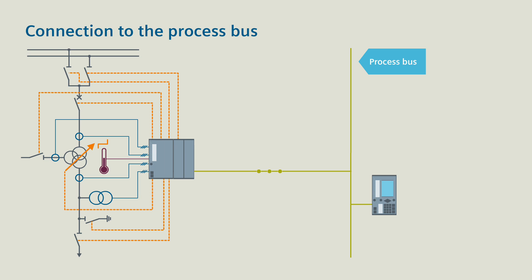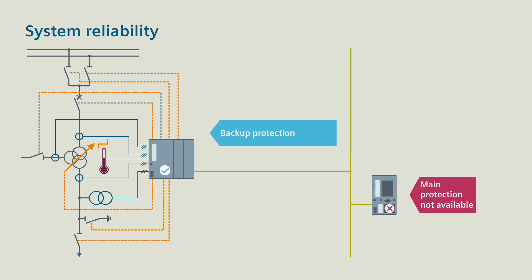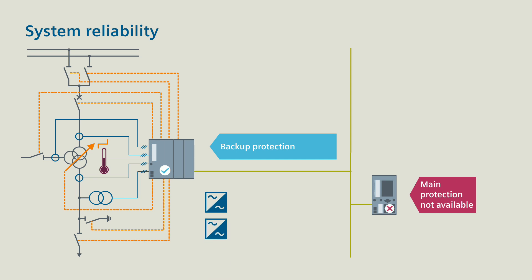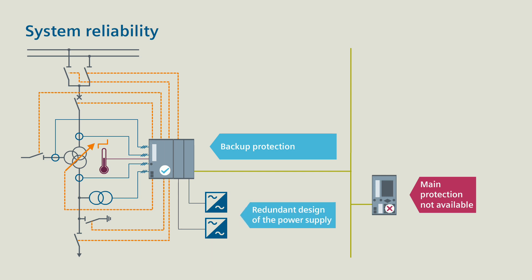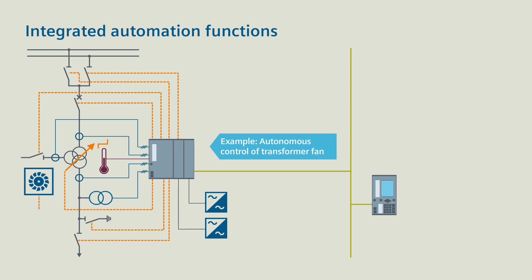The SIPROTEC 6MU85 merging unit can do even more. If the main protection is not available, the backup protection integrated in the merging unit provides the necessary system functions. You get additional system reliability with a redundant design of the power supply. And with integrated automation functions, the merging unit can take over the control of the transformer fan completely autonomously, depending on the measured temperature, for example.